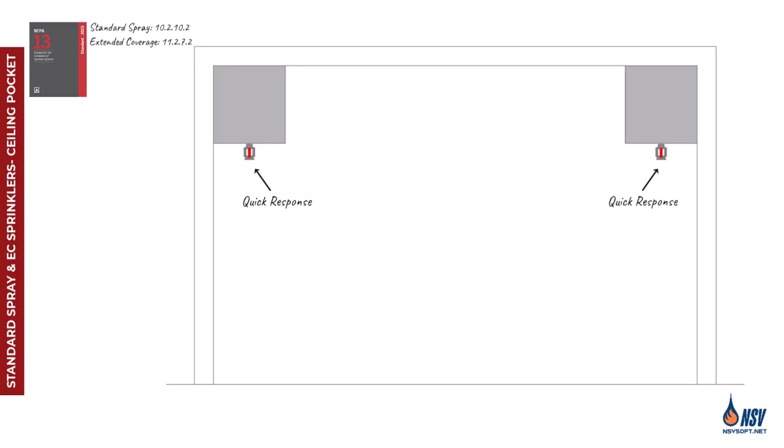Where quick response standard spray or extended coverage sprinklers are installed throughout the compartment, NFPA 13 permits omitting sprinklers in a ceiling pocket, provided the lower level sprinklers can cover the entire floor area and all of the following conditions are met.